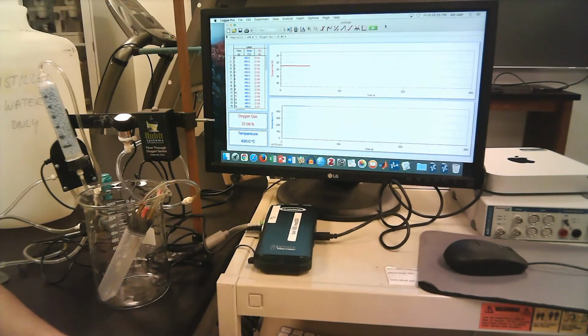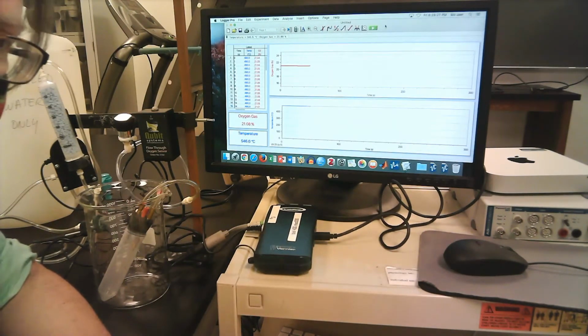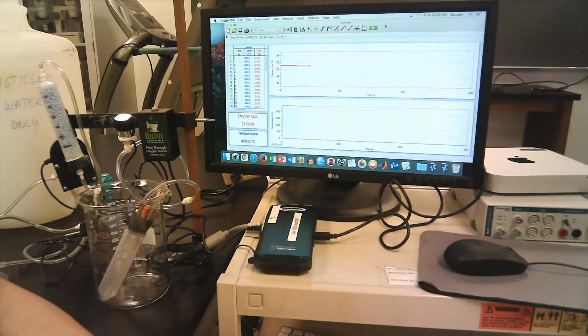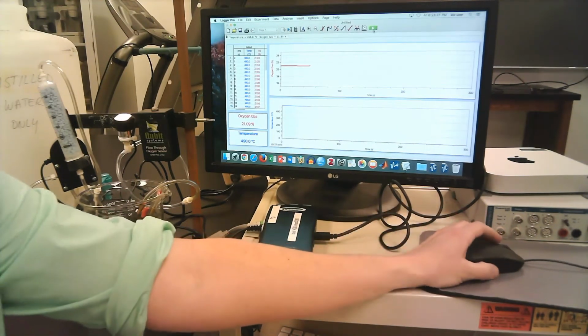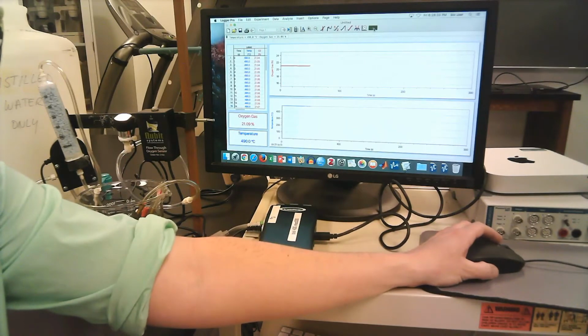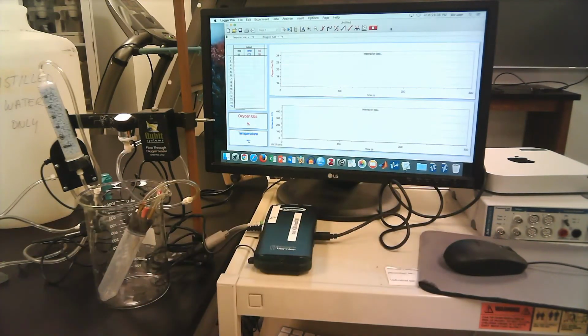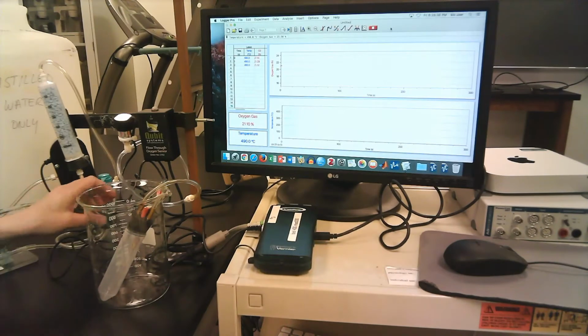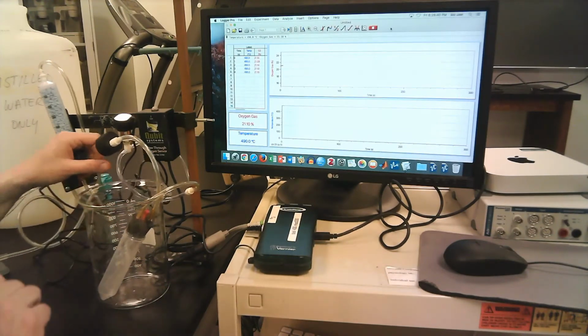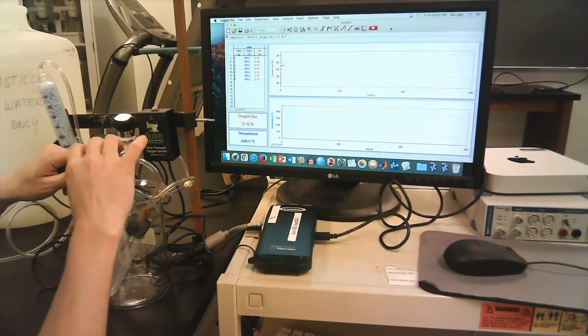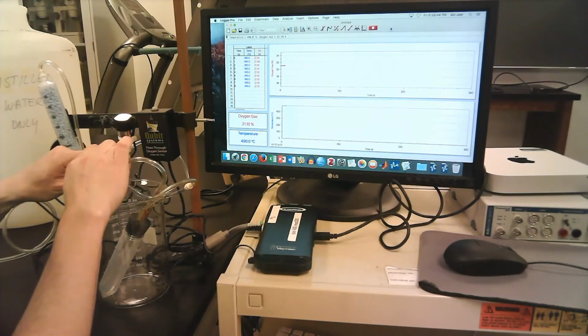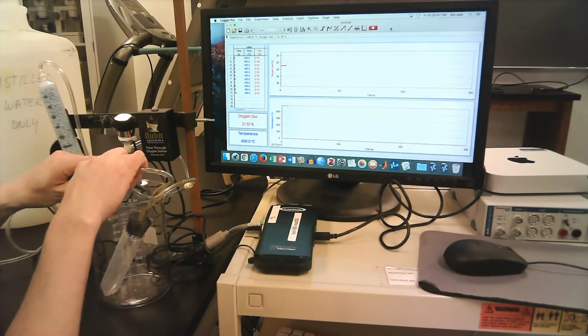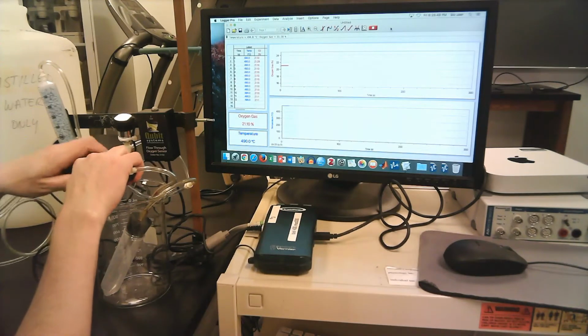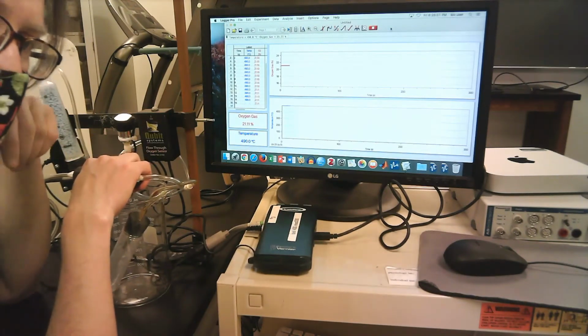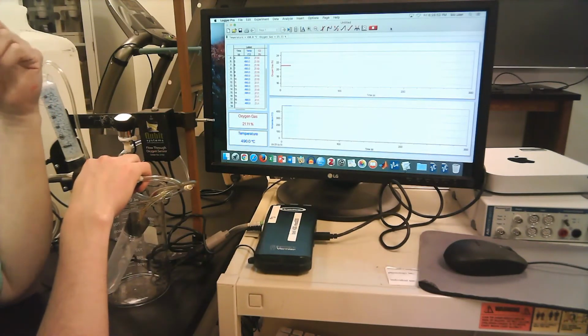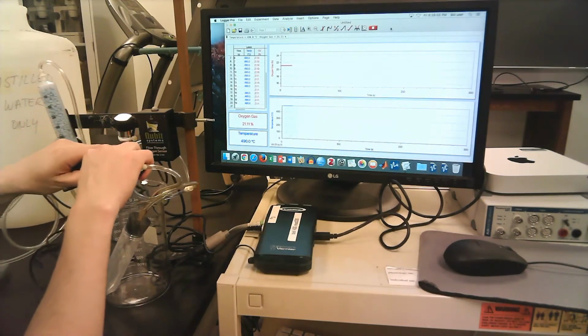Okay, so once you've got your baseline data, the next thing you're going to want to do is put your animal in the chamber and continue collecting data. So what I'm going to do here is start collecting data, and rather than putting an animal in the chamber, I'm going to breathe into this chamber a couple of times, just as a sanity check to see, is this going to give me a reliable measurement? This is actually a very common method for checking to see if your chamber and everything is behaving as you'd expect it to.